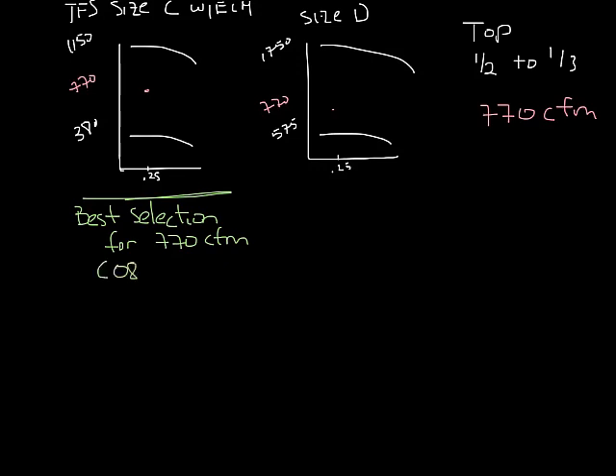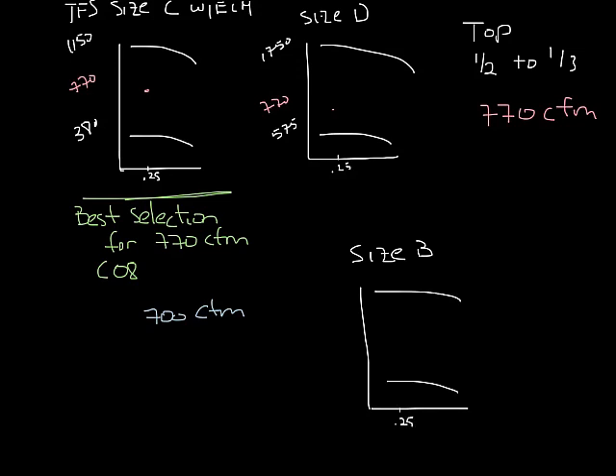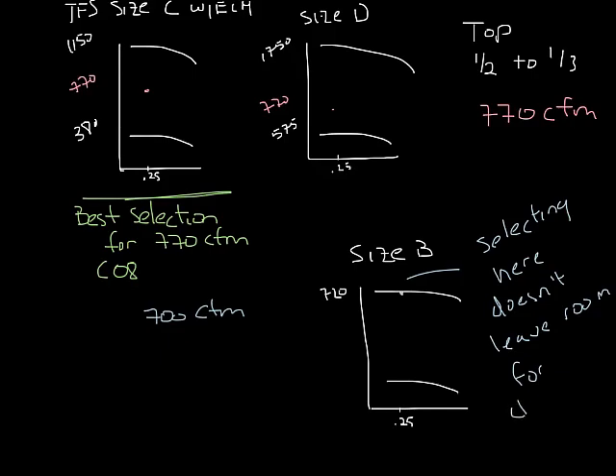Now if you needed 700 CFM, there would actually be 3 possible unit casing sizes that would work, because the size B TFS with the ECM motor has a fan curve that has a maximum at 720 CFM at 0.25 inches. But in this case, you would be right at the top of the fan curve. Selecting here doesn't give you much leeway in case the pressures are higher than expected or your airflow requirements change.